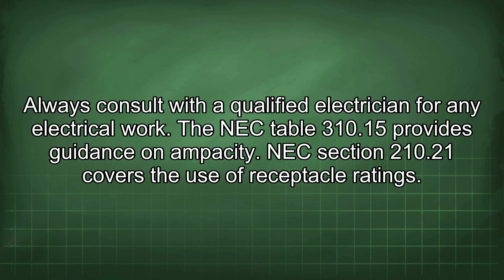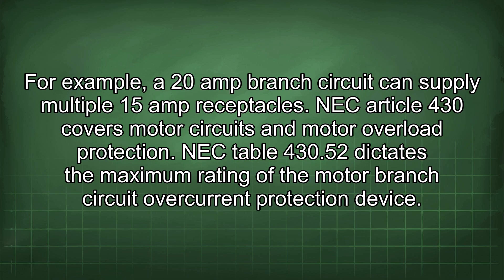NEC Table 310.15 provides guidance on ampacity. NEC Section 210.21 covers the use of receptacle ratings — for example, a 20A branch circuit can supply multiple 15A receptacles. NEC Article 430 covers motor circuits and motor overload protection, and NEC Table 430.52 dictates the maximum rating of the motor branch circuit overcurrent protection device.